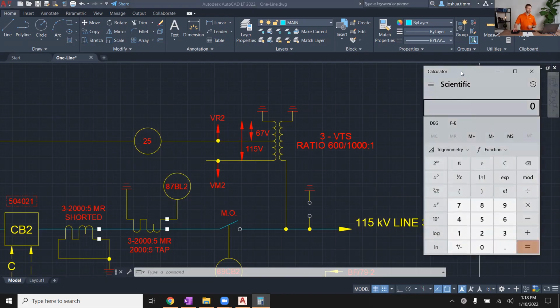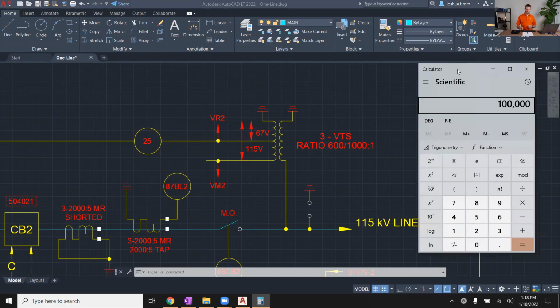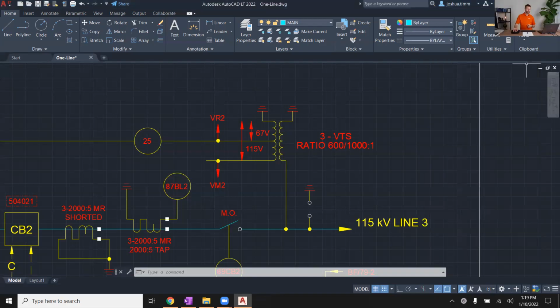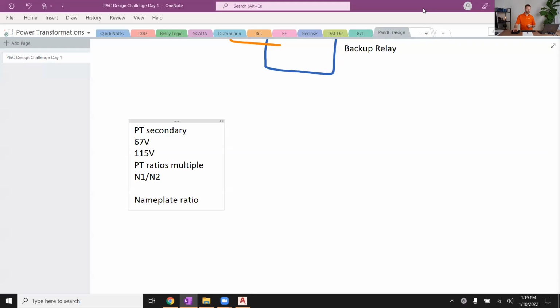In that case, if you had a 100 kV line divided by root 3, that's 58 kV line to neutral, you're still going to have that 1,000 to 1 ratio. That's a fixed physical quantity of that PT. So divide by 1,000, and you would expect to see somewhere close to 58 volts on the smaller secondary tap for a 100 kV system, even though it's a 115 kV PT. Did that kind of clear up your point there, Sean? Yeah, I think that's good. Thank you. Great question. You are correct. I've seen that sort of situation before.